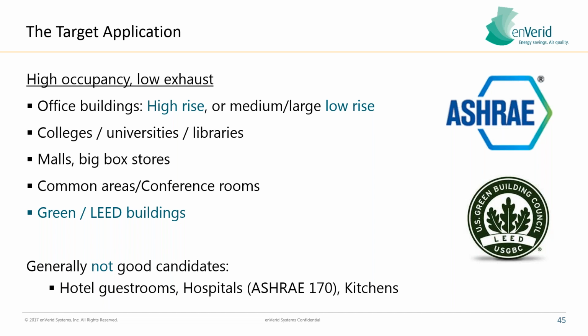So generally not good candidates would be hotel guest rooms, hospitals with ASHRAE 170, or kitchens. We might be able to do the cafeteria, which has lower exhaust than the kitchen. We might be able to do the administrative wing of a hospital because those will be classified as offices. And we might be able to do like the ballroom or the common area of a hotel, just not the guest rooms because they have such high exhaust.